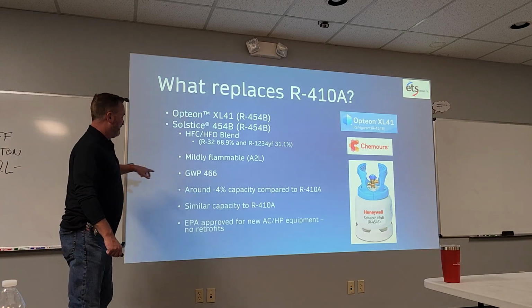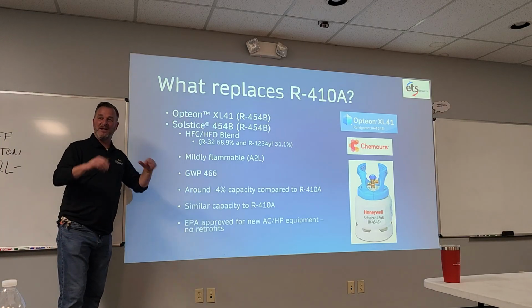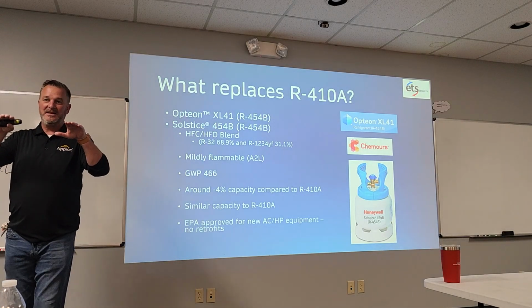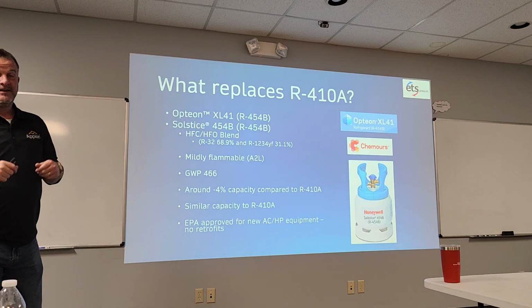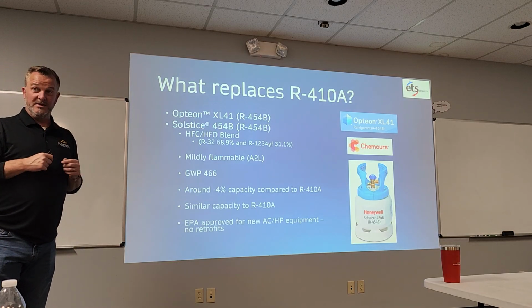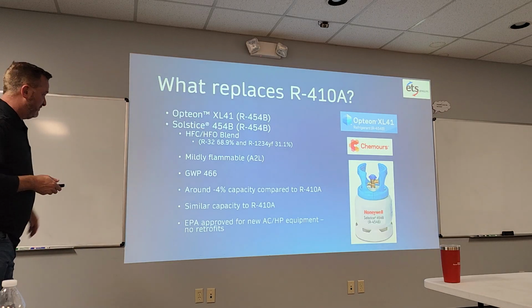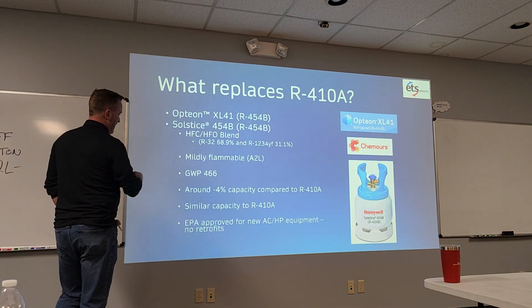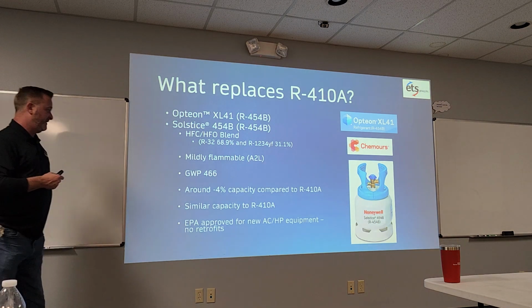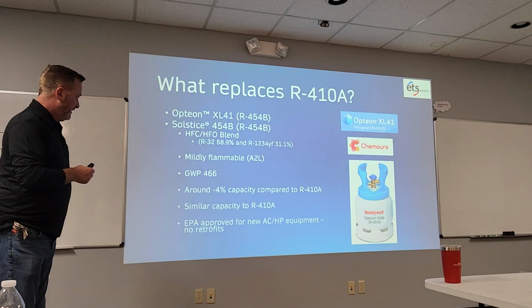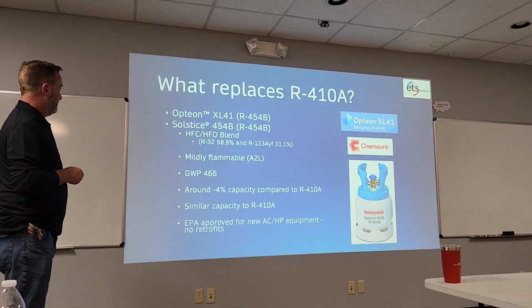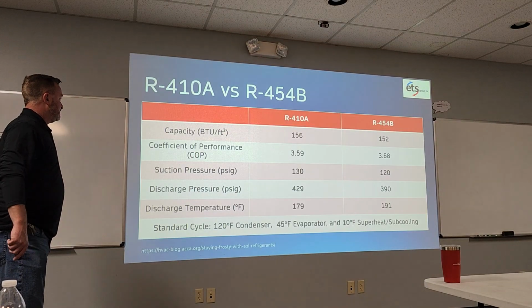I think when they first marketed it, that's where that 600 GWP limit came out at 2030. They were saying, hey, as of 2030 you won't be able to use this, which was kind of BS, but that's what they do. It's got around negative 4% capacity compared to 410A, very similar still, and again, EPA approved, so these two are good to go.